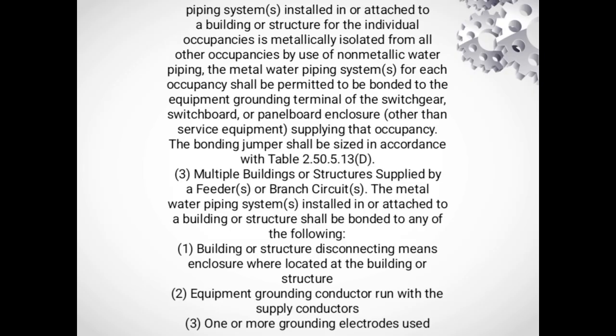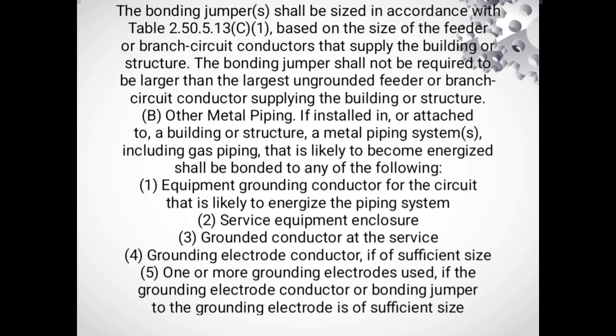Number 3, multiple buildings or structures supplied by a feeder or branch circuit. The metal water piping system installed in or attached to a building or structure shall be bonded to any of the following. Number 1, building or structure disconnecting means enclosure where located at the building or structure. Number 2, equipment grounding conductor run with supply conductor. Number 3, one or more grounding electrodes used.